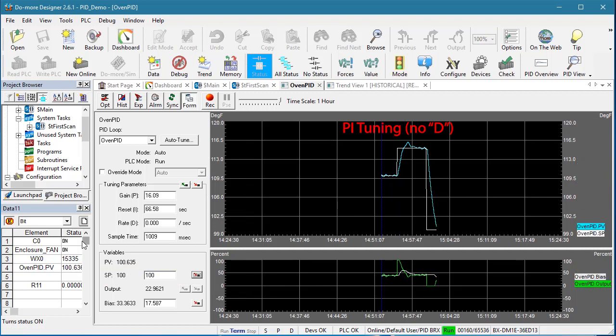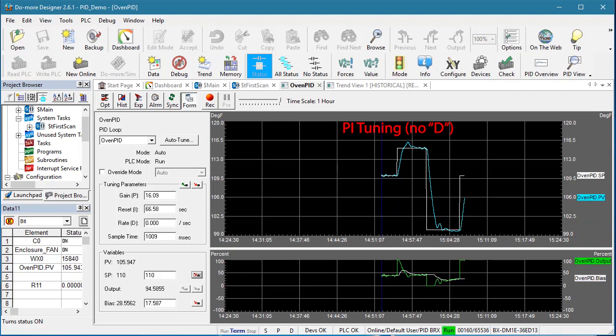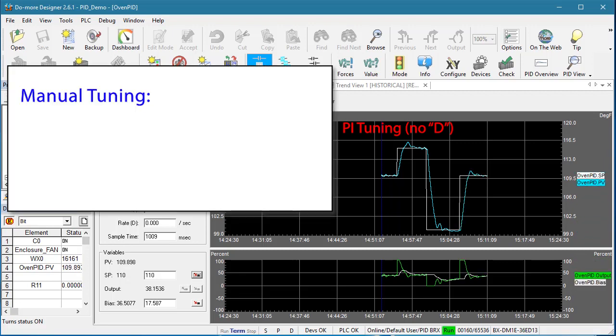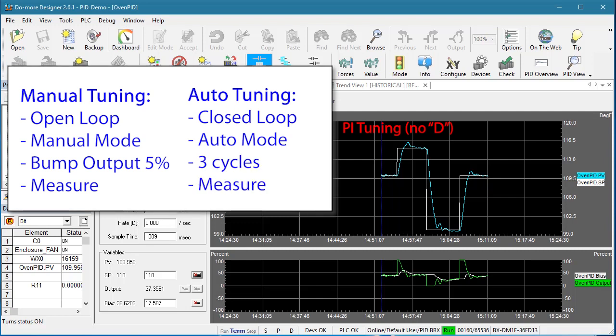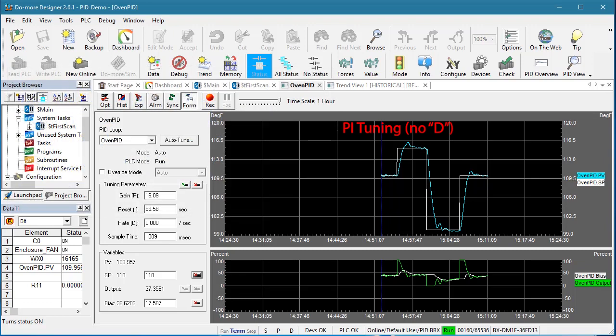I'll go to 100 degrees like we did before and back to 110 degrees. The cool thing about this manual method is it's an open loop tuning. That is, we put the PID function in manual mode, did a 5% bump and took some measurements. All the tunings we did in the previous videos were closed loop. They actually used the PID function in auto mode to monitor the process variable, do the three cycles and make a decision. Which begs the question, how does this manual tuning compare to the auto tuning we've been doing?